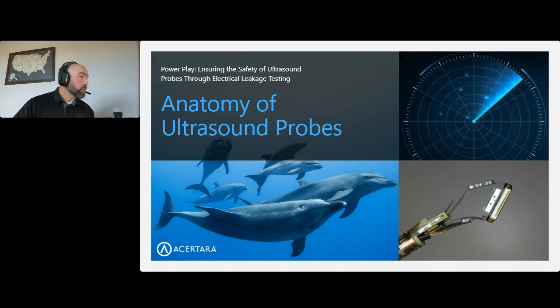Let's see. So we talked a little bit about how the ultrasound probes use the piezoelectric effect to create ultrasound. So I'm not going to go over that again. But it is just important for me to reiterate, these electronics are really sensitive. They're very fragile. And so you want to be very careful with those, and inspecting the lens, the housing, the tip on a TEE probe, the lens on a TEE probe, to make sure that those are physically intact. You should know what they look like when they're good, because knowing really well what they look like when they're in great condition is going to help you to find those times when they don't look quite so good.